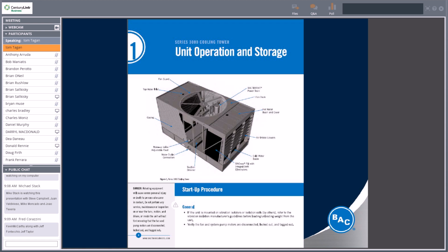But again, as we move on, showing this drawing again, it's just kind of a breakdown. This is, as an example today, I'm using the BAC Series 3000 cooling tower. It's a 2-sided air inlet induced draft cross-flow cooling tower, similar to the Marley NC tower and the Evapco XS, the Axis tower. So this is kind of the workhorse of the industry. I would say probably 60% of the cooling towers you'll see will be similar to this design across New England.